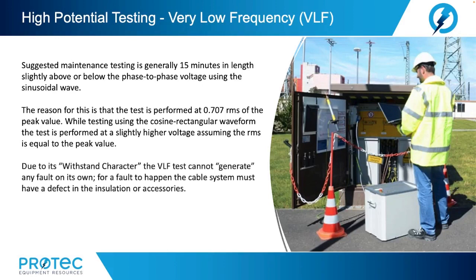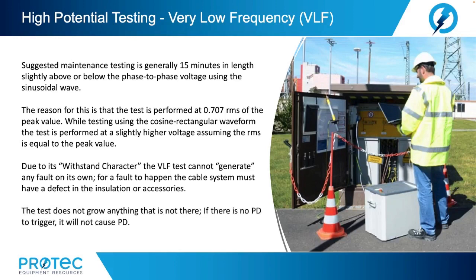Due to its withstand character, the VLF test cannot generate any fault on its own. For a fault to happen, the cable system must have a defect in the insulation or accessories. The test does not grow anything that is not there. If there is no PD to trigger, it will not cause partial discharge.